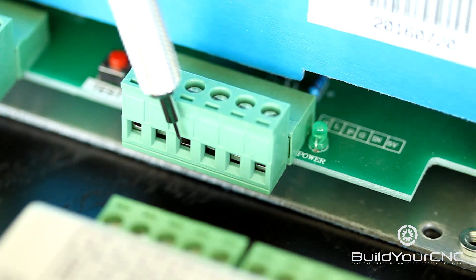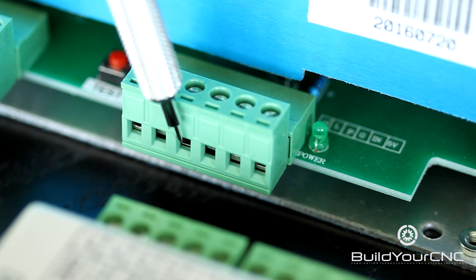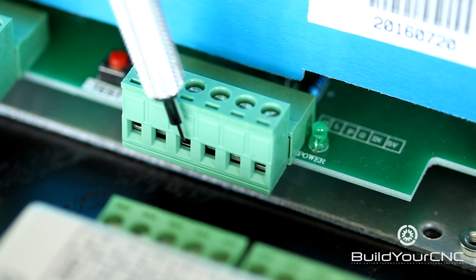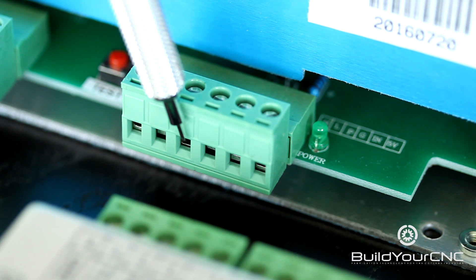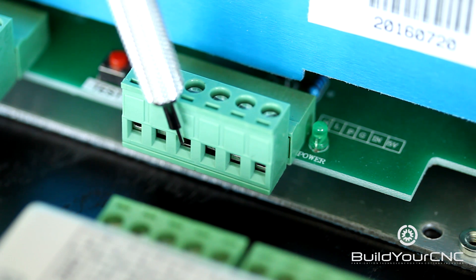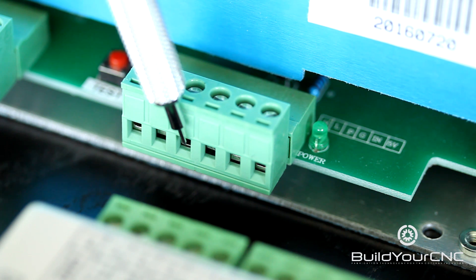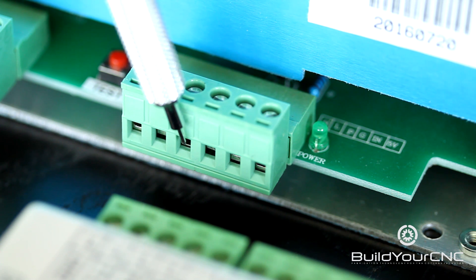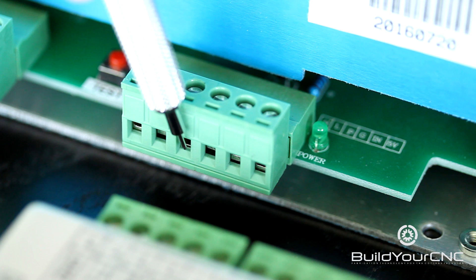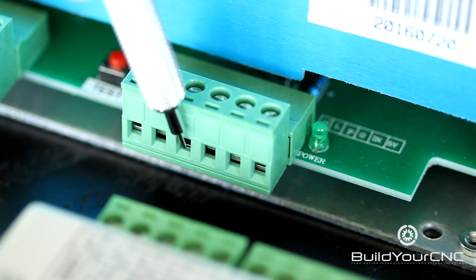The next terminal is the water protect, or a signal that will power off the laser in case of a water leak or some other sensing that the laser may not be operating in a safe condition. If you apply 5 volts to this terminal, the laser will turn off.